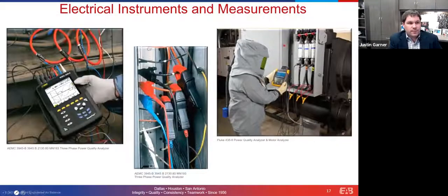All right, so we're going to go into a little bit about electrical instruments and measurements in the field. I'm going to talk about safety here in a minute, and I'm going to reference back to this picture of this person that looks like they're in a bomb suit, but this is some arc flash protection clothing. I'm going to talk about that in just a moment. And then we've got just a few other pictures here. These are current clamps that we very frequently use. This is a smaller size. Then you see some larger coil type clamps here that we use with a power meter. I'm going to talk about that a little bit more in detail. But just recognize when I say an amperage clamp, these are the types of things that we're referencing. And hopefully everyone that's out there doing TAB work knows what I'm talking about.